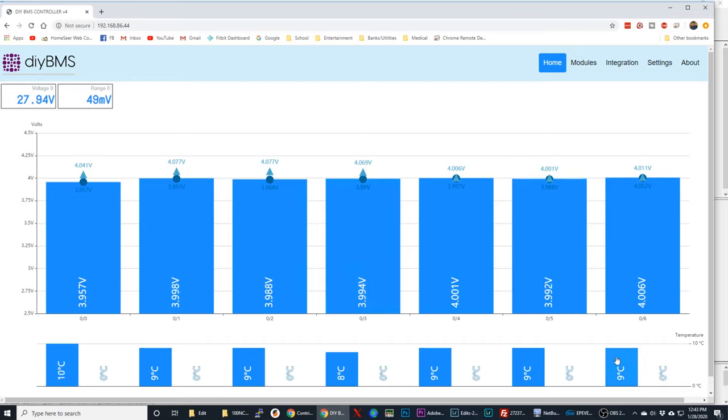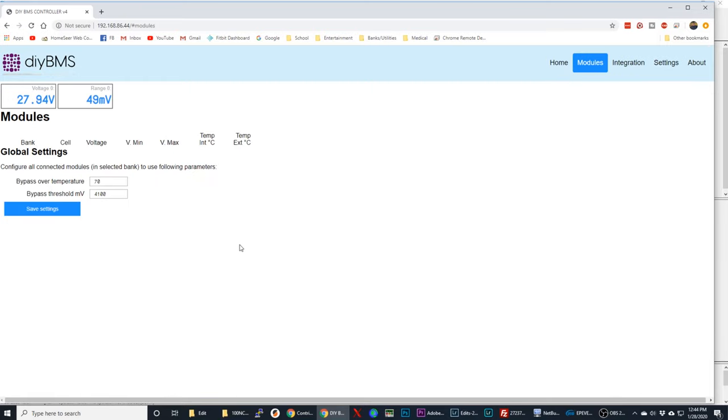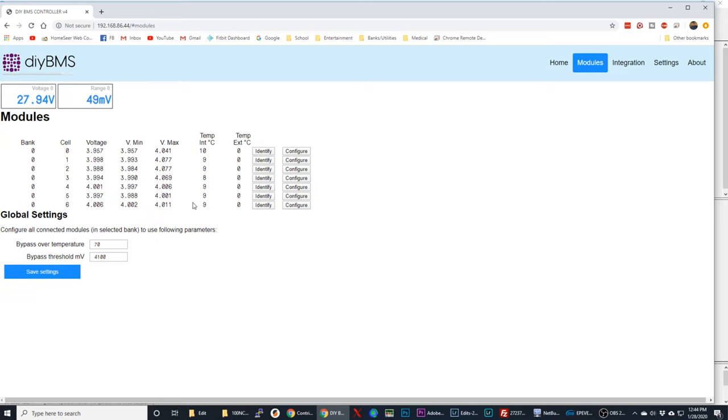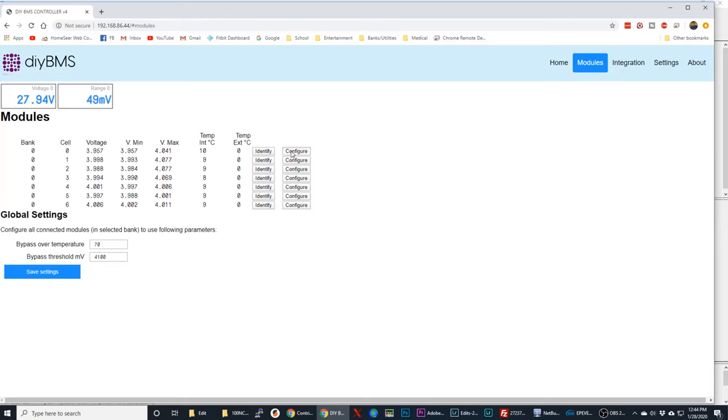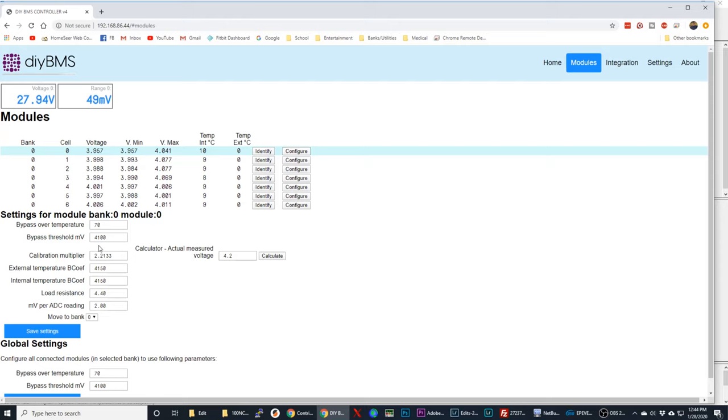You can go into the individual modules and what you want to do here is you want to check the capacity of each of your cells and make sure it's calibrated. You want to go in and make sure that each cell is what's being represented on here. You just go into the configure settings and just take your multimeter, check what your real value is, and then it will come up with a multiplication factor for you.